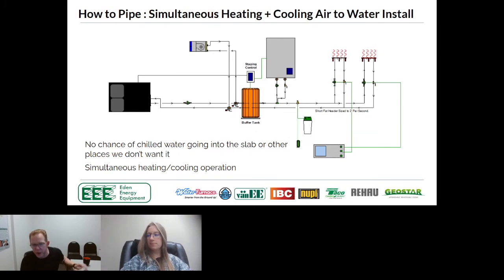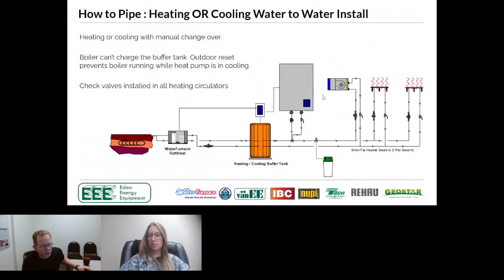Same conversation we had where the cooling is downstream, where the cooling is here, and we assume the homeowner will turn the heating thermostats off, so it's no big deal. No chilled water will go there. So whether you're using two diverting valves or one diverting valve, I'm not saying one is right or wrong. Both are certainly doable. It's kind of the conversation of piping on the return or pumping on the return or pumping on the supply. Depending on what appliance you have, is it a cast iron boiler? Is it a condensing boiler? Where's your expansion tank? You can make a lot of arguments of which way it should be pumped or shouldn't be pumped.